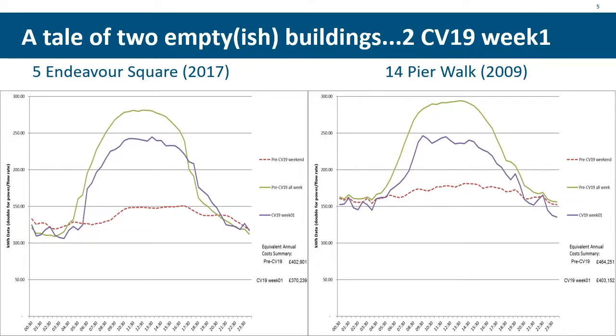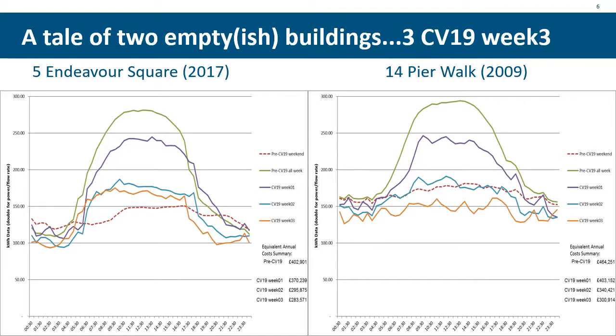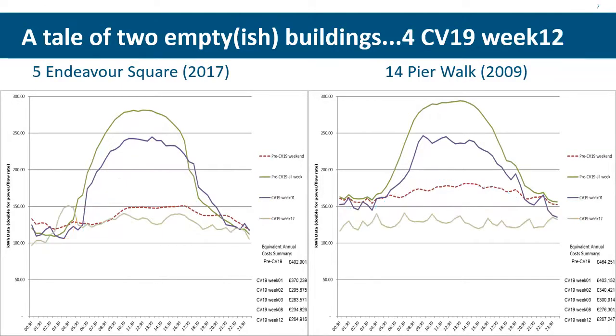Well, week one, we hadn't managed, the people had effectively left, and the BMS was just doing what it was doing before. By the time we got to week three, we'd actually done some changes. We'd managed to find the fans that were still running at the floor occupancies. These are all demand-driven buildings, so the floor occupancies were set at 8 to 6 still, as if everyone was there, but nobody was. So a lot of those loads were the air handling kicking in, which we managed to switch various things off.